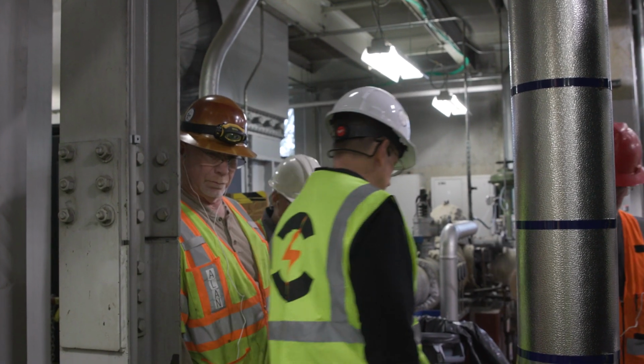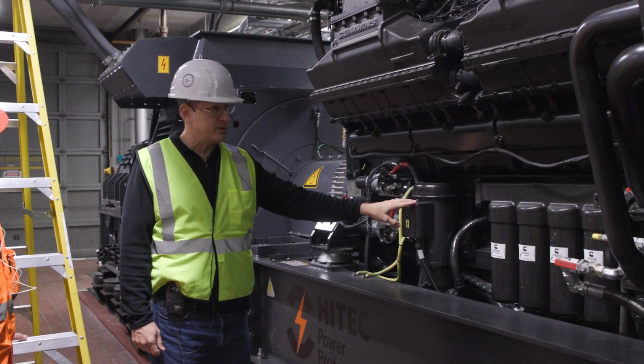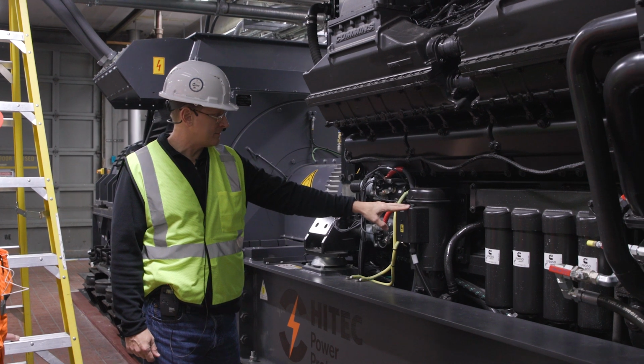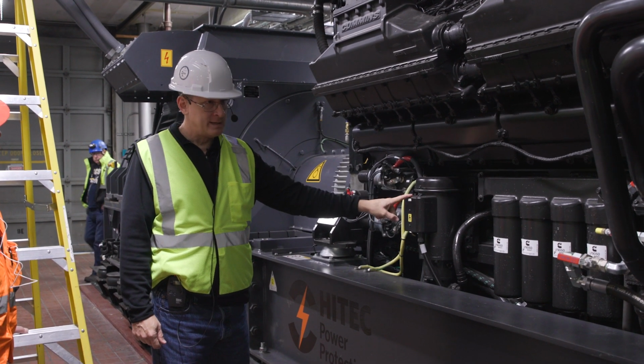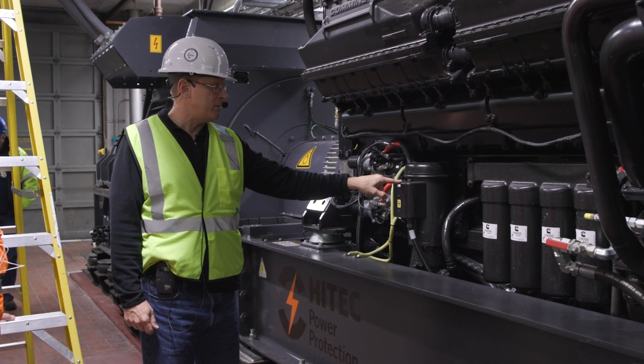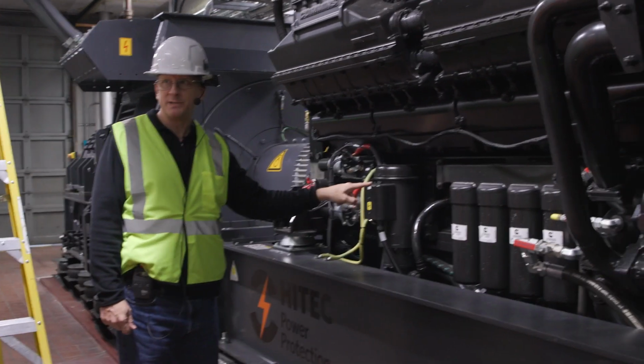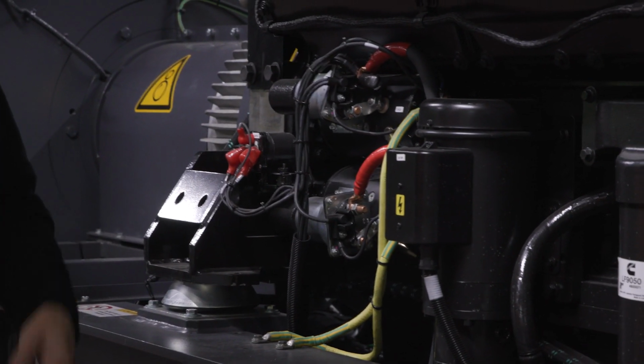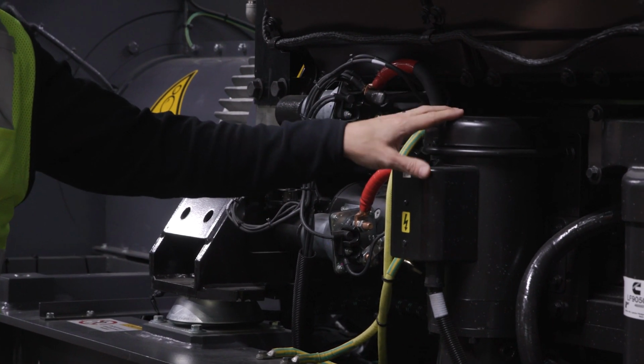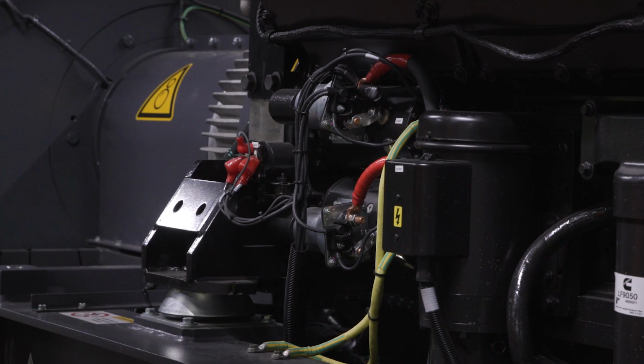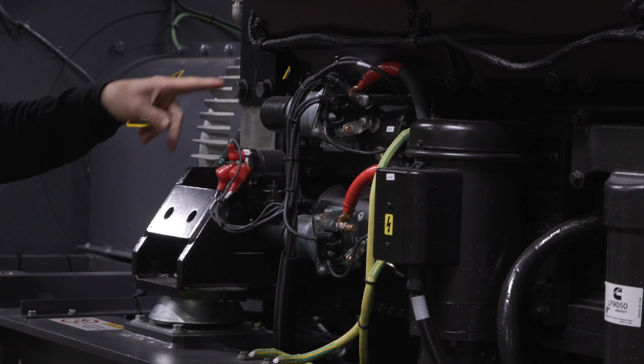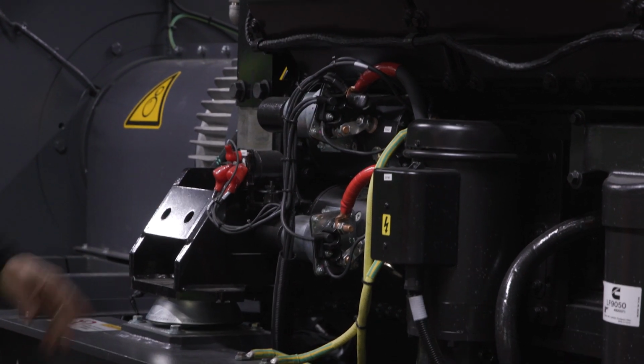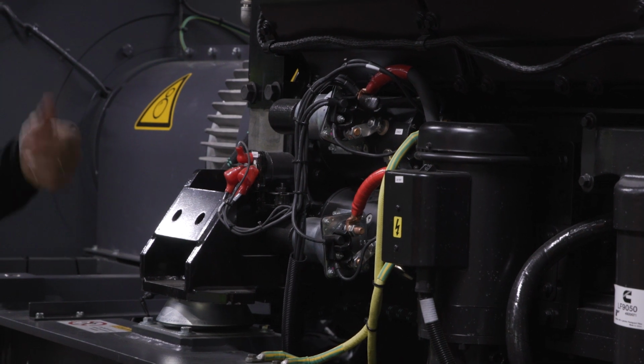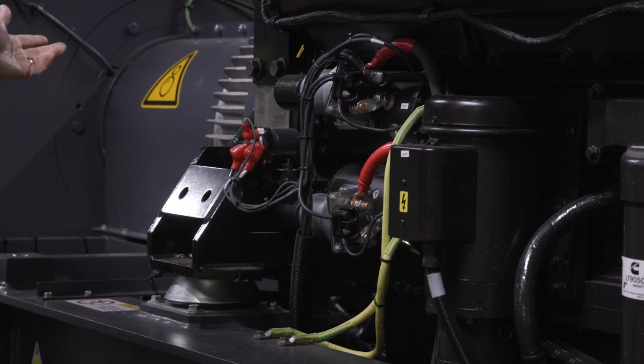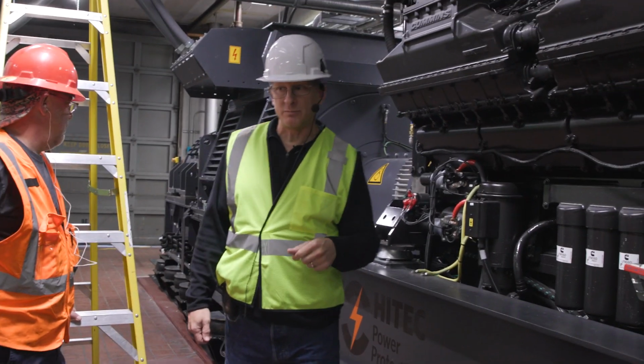And then also on this side we've got the Prelube Pump. So this is the Prelube Pump. It as well is sourced from the 45 kVA transformer in the switchgear through the UCP. So every so often, maybe once an hour or so, it'll run for a couple of minutes just to maintain lubrication pressure and keep the oil lubricated. It's very noisy, so that's the noise that you'll definitely hear when this thing is running. And then you've got your start motors. You've got 2 start motors for the engine connected to your batteries and your RSP for turning the flywheel upon starting. Clutch again. Clutch has another side glass. Has side glass on both sides.